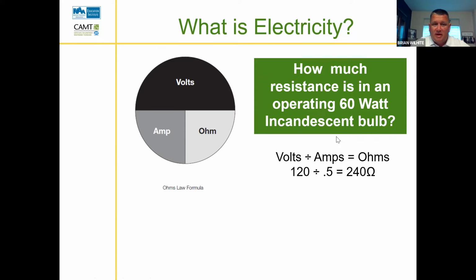So that's the mistake that's often made, Bryce, is that we could use continuity. With those elements, if everybody knows what an electrical element in a water heater looks like, it's almost like a small version of a copper pipe. And if you've ever seen a copper pipe freeze with water in it, they split. They don't break all the way through, they split. Now, sometimes our elements inside our water heater break all the way through, but sometimes they split like that copper water pipe that's been frozen. And if they split like that, could we still get continuity, Bryce? 100%. Nick, would that element be good though?